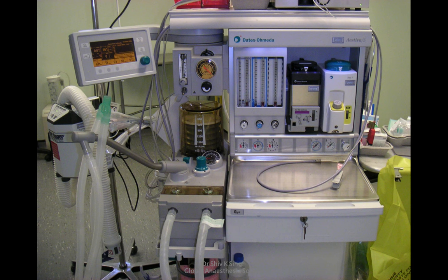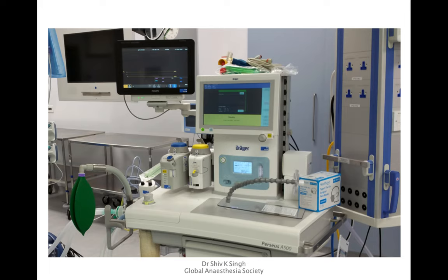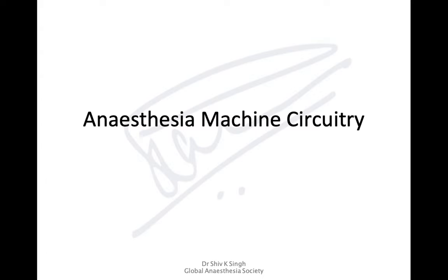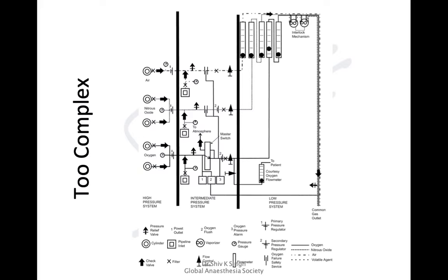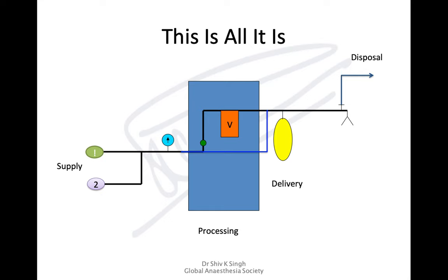The latest machines don't even have the flow meters we had in older machines — a lot of it is electronically controlled and computerized. Anesthesia machine circuitry can be quite complex and difficult to understand, but we're going to simplify it. Any modern anesthesia machine includes the supply, which comes through the pipeline from vacuum insulated evaporators or a bank of cylinders.